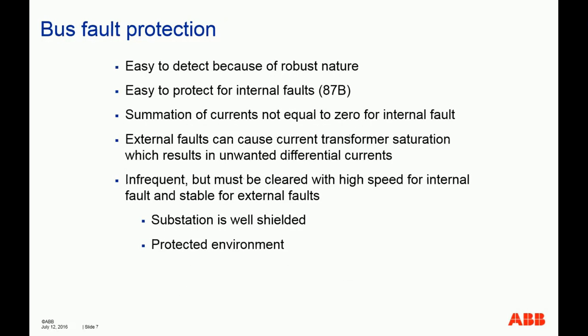Bus fault protection is easy to detect because of the robust nature. Robust nature means typically the fault current is pretty high, so it is easy to detect, and easy to detect for internal faults. Typically, we use the differential principle: the summation of the currents is not equal to 0 for an internal fault, and needs to be near 0 for an external fault. We use this principle to distinguish whether the fault is internal or external.